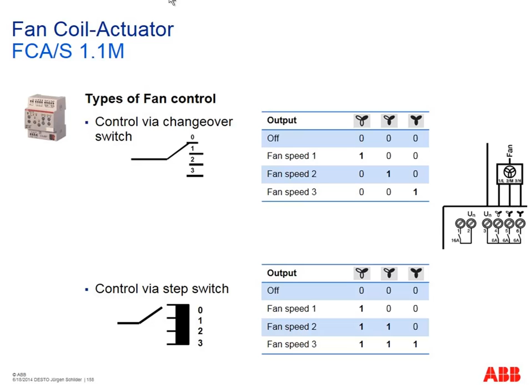The next fan actuator we launched is the Fan Coil Actuator FCA 1221. Here we have in principle the same hardware device. The only difference is we have three binary inputs, one more. And instead of our electronic outputs to control our electrothermal or motoric valve drives, we have analog outputs between 0 and 10 volt.